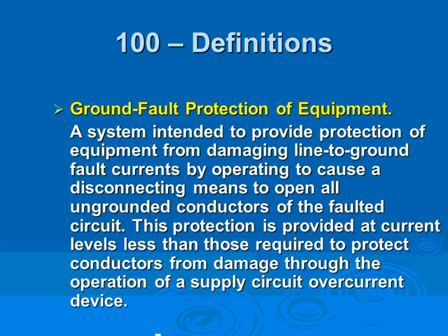It's recommended, but not required. 1,000 amp or more. If your voltage is 480-277, this is the worst arcing and sparking and blasting and shocking voltage that you can encounter, right? Worse than 208 and 240.